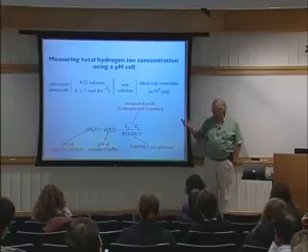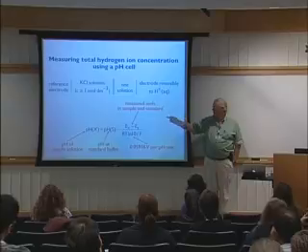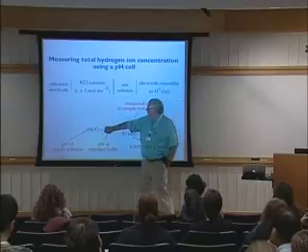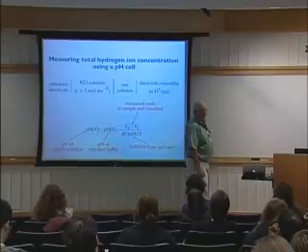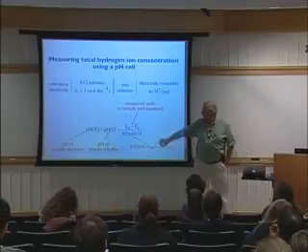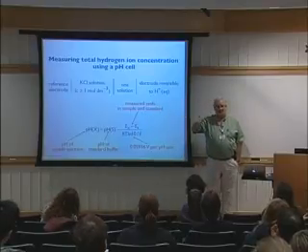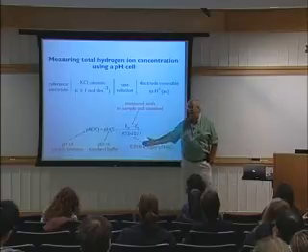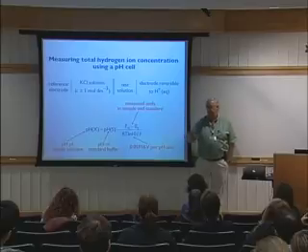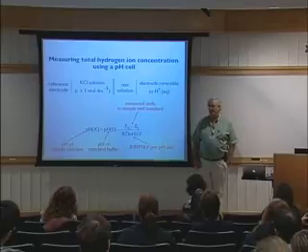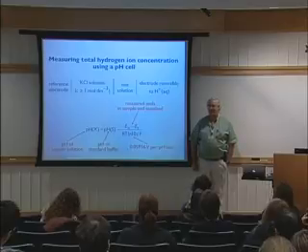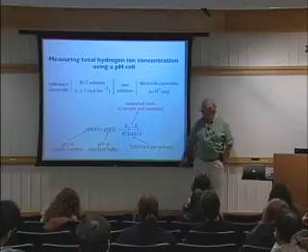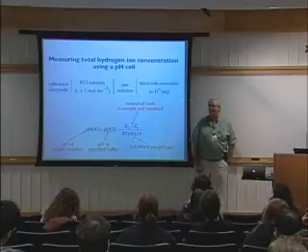In principle, if you had two buffers, that is, not only did you know this one, but you also knew that one as well, then you could test whether this was a consistent system, and your most likely place to ascribe blame normally is, you say, look, this buffer says pH 4, this buffer says pH 7, but it's only 170 millivolts between the two, not 180. Couldn't I just put some fiddle factor and change that term?